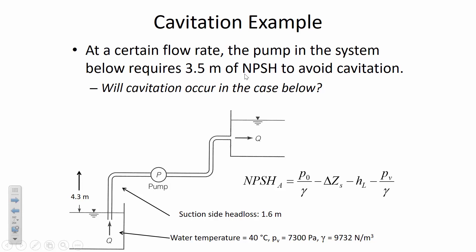For the NPSH calculation, P₀ is absolute atmospheric pressure — 101.325 kPa — not gauge pressure. This is the starting point from which all other factors reduce the available suction head.